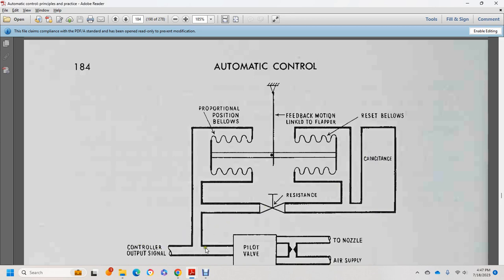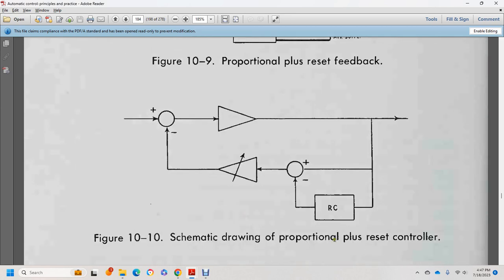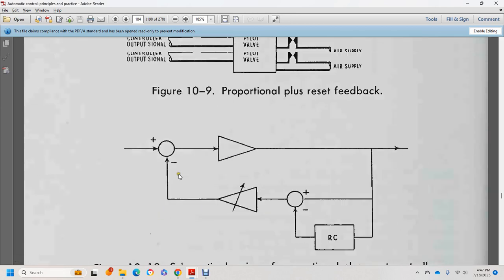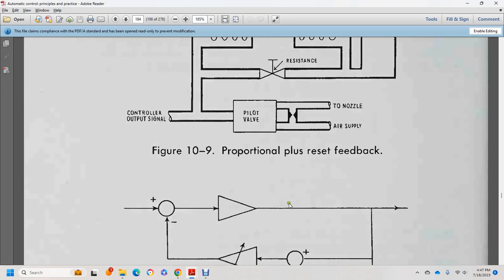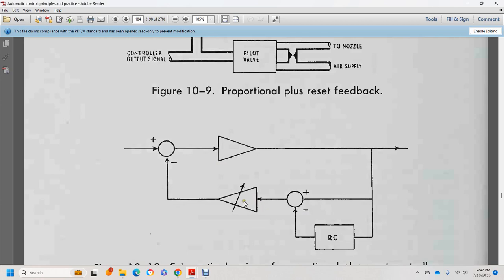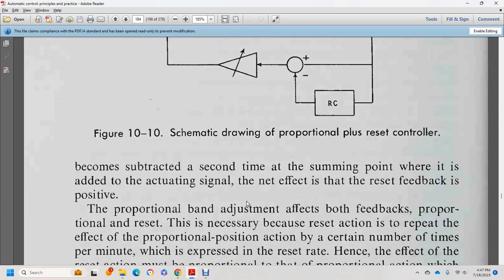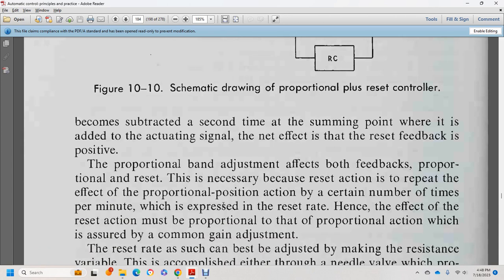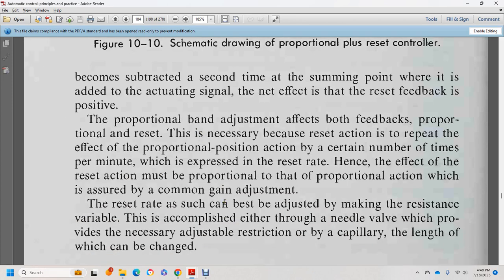The schematic shows proportional plus reset, going from supply to the amplifier, through the RC pilot valve and needle valve. The reset feedback is positive at the actuating signal level; the proportional band adjustment affects both feedback paths. The effect of the reset action is to repeat the effect of the proportional position action a certain number of times per minute. The reset rate is adjustable by changing the resistance through a needle valve or capillary.